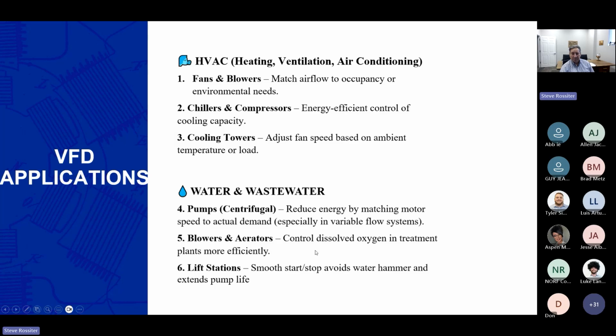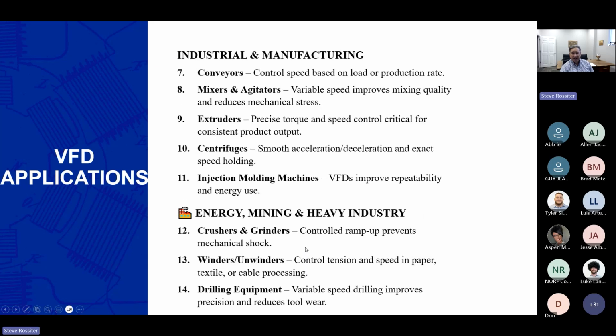Water and wastewater pumps, again, whether it's a municipality or a local HOA development, most all of those are using variable frequency drives to maintain pressure in the system, as well as the right amount of flow on need. Same thing with the lift stations, and of course, other advantages of the variable frequency drive are similar to your reduced voltage starters or soft starts. You can ramp those in a way that avoids water hammer, and can decelerate the same way to have many advantages. Of course, in the manufacturing area, a lot of that really is important in reducing the wear and tear on the drivetrains, or in the case of a bottling factory, actually having a ramp that's optimized to not drop the bottles off the conveyor, but optimize the speed to get it up to speed.